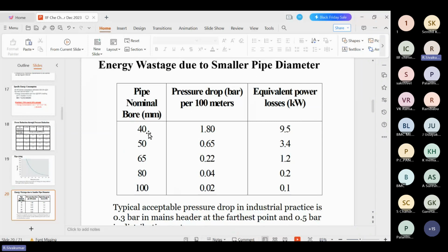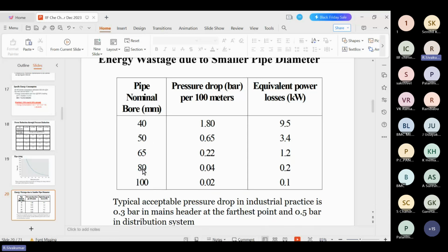For a nominal bore size of 40 mm, the rate of pressure drop is 1.8 bar for every 100 meters. It is equivalent to 9.5 units lost. Similarly, for the same generation, if an 80 mm pipe is used, the pressure drop is only 0.04 bar. Here 40 mm is 1.8 bar, and 80 mm means 0.04 bar. That much pressure loss is reduced as the pipe size increases, and the power loss is also only 0.2 instead of 9.5.